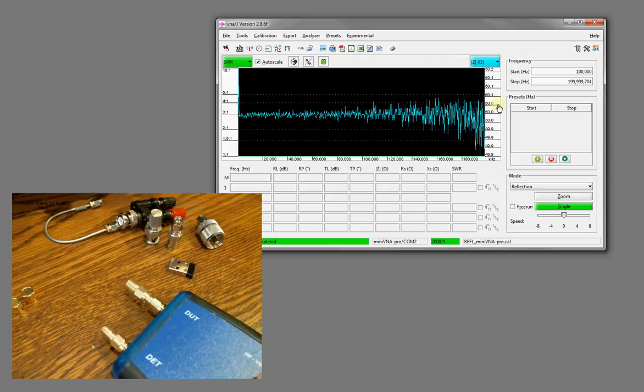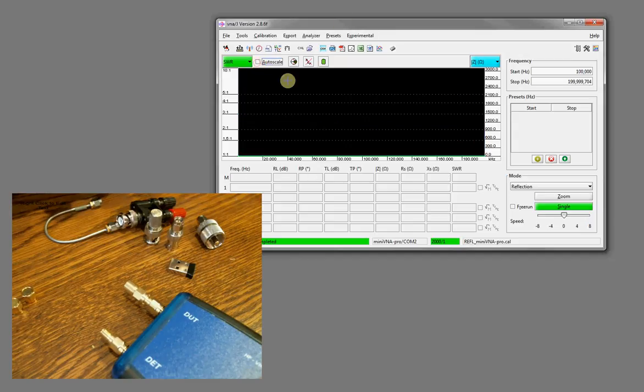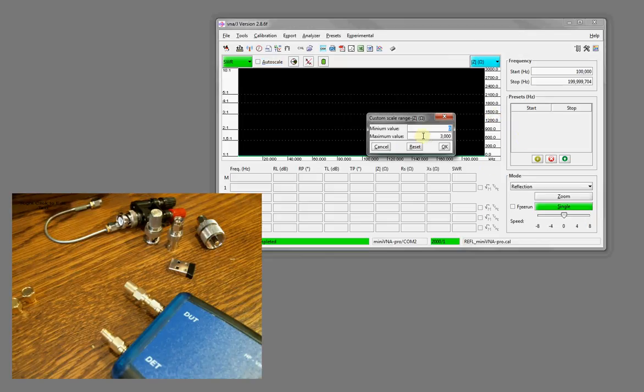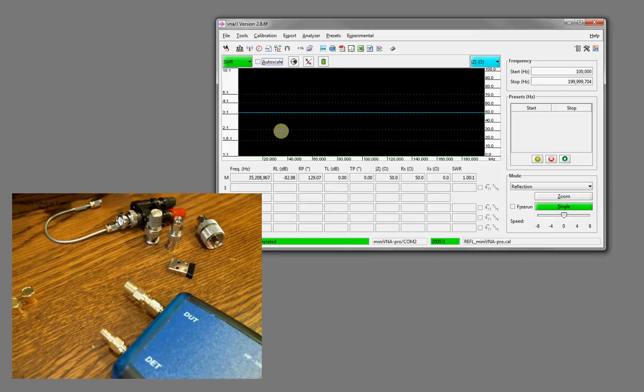If you notice on the scale, it automatically scales the signal, in this case the impedance, from 49.8 ohms to 50.2 ohms. So you see the line going everywhere, but you're looking at it very closely. If we turn auto scale off, the line disappears because it goes from 0 ohms to 3,000 ohms. So let's change it to, let's say, 100 ohms or something like that. And there you go. You can see the signal.